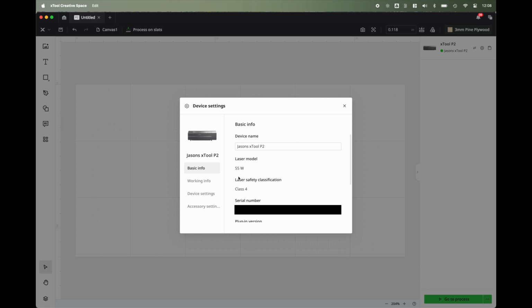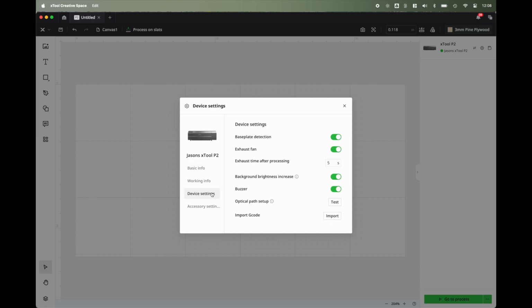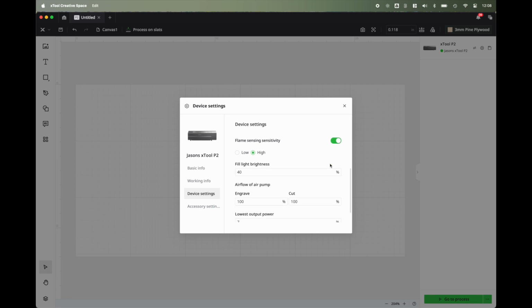I then launched the settings to look at the different options, and one setting you may need to adjust is the exhaust fan. This toggle determines whether the internal exhaust fan is used. If you have another exhaust system, like an in-room filtration system or a larger exhaust system like I'm using, you need to turn off the internal exhaust fan, or else you'll create a pressure difference with two different fan speeds, which will reduce your smoke exhaust performance.